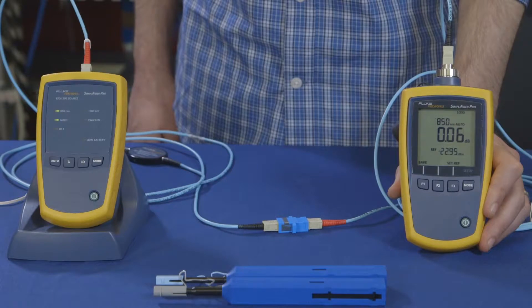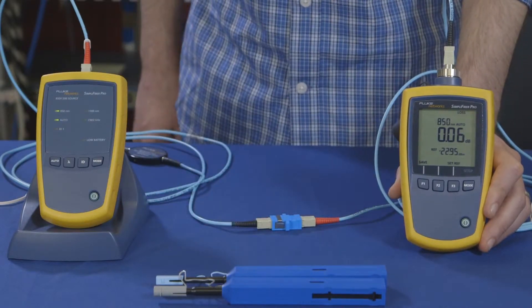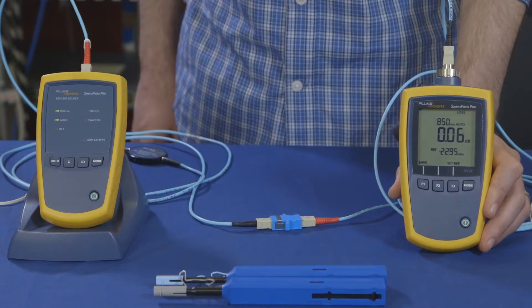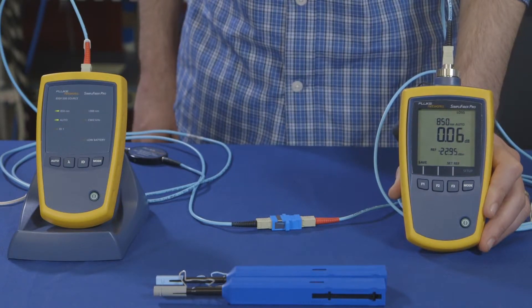Using a coupler, we've attached the second TRC, and we'll run a test to verify they're good. We should not get a loss greater than 0.15 dB. We're now ready to test.